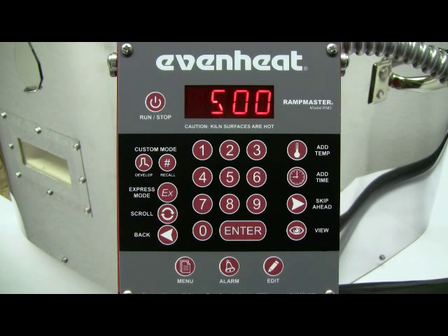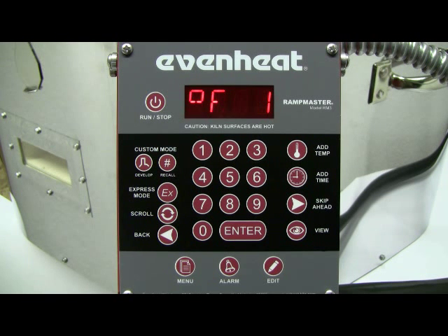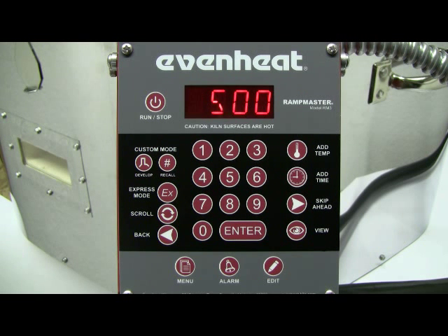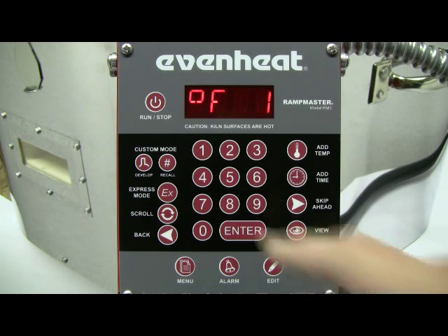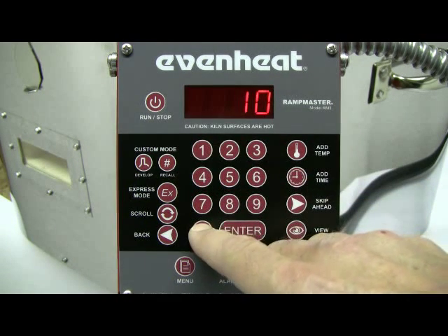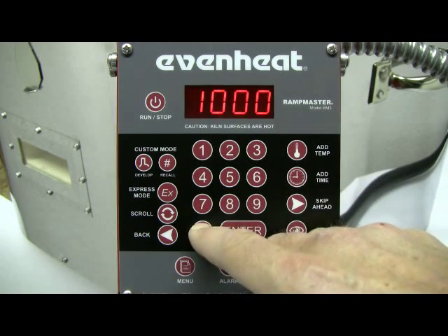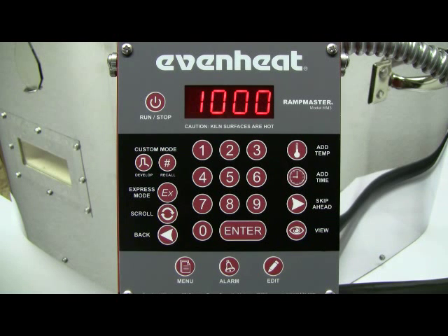The display now reads degrees Fahrenheit 1. The RampMaster is asking for the desired temperature to be reached in segment 1. For our example, we want to go to 1000 degrees. Type in 1000, then press the ENTER key to store your choice.